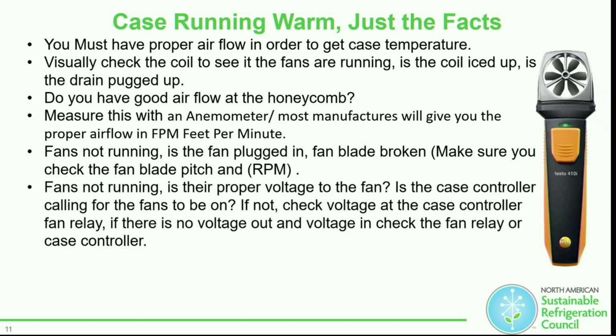Fan's not running. Is the proper voltage going to the fan? Is the case controller calling for it to be on? If not, check the voltage at the case controller and the fan relay, and make sure there is no voltage. If there is voltage in but no voltage out, check the fan relay or case controller.